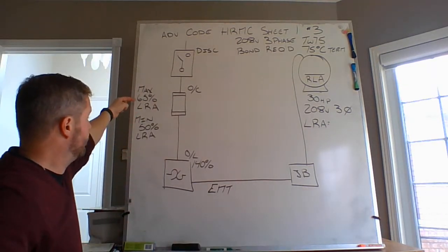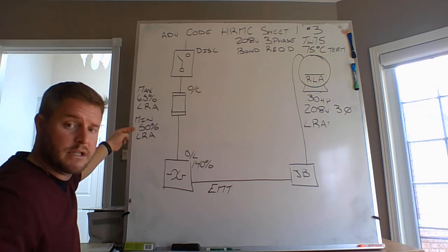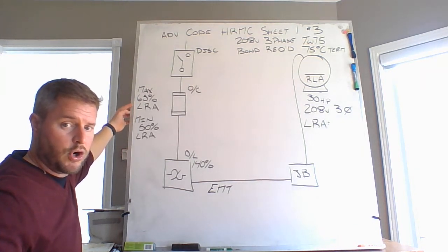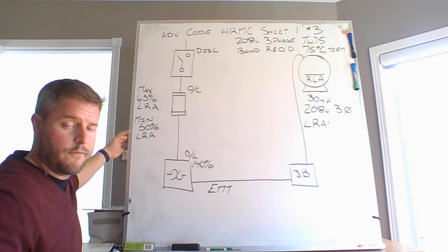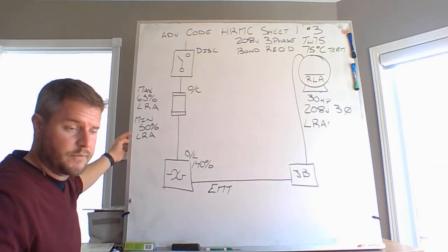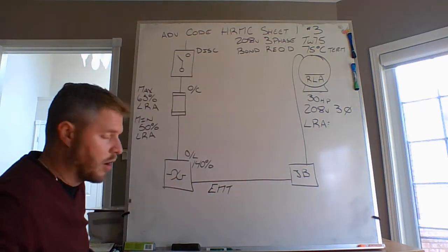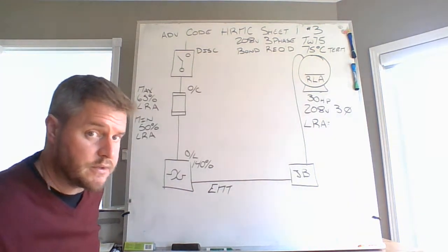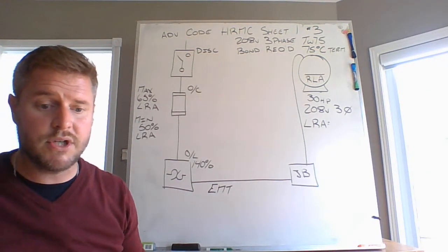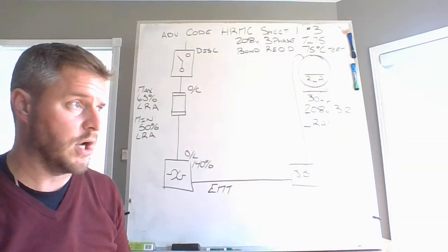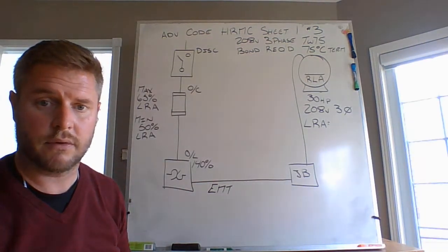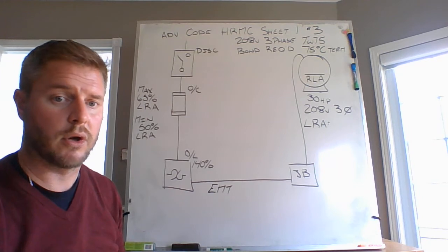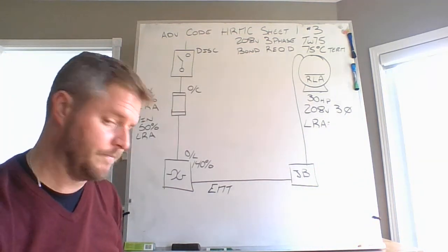And then I kind of plainly wrote this out over here for minimum and maximum ampacities of your overcurrent device. Maximum being 65% of the locked rotor current, and 50% of the locked rotor current for your installed minimum fuse size. Okay. Also across the board, you're at 140% for your overload calculation. Okay, so record these values. Take a second, new sheet, look at those. Maybe make a note, jot that down for your overloads, overcurrent component: 30 horsepower, 208 volt, 3-phase, and I want to look at my rated load current and my locked rotor current.